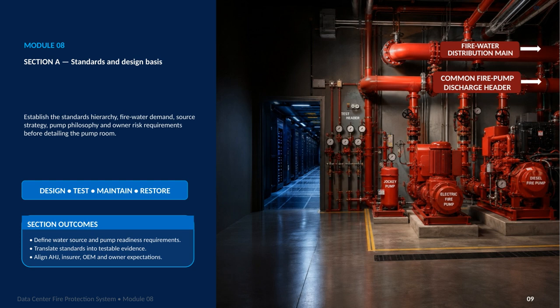First, we'll define what makes the water source acceptable and what readiness requirements apply to the pumps. Second, we'll translate standards into testable evidence, so compliance can be demonstrated rather than assumed. Third, we'll align the expectations of the authority having jurisdiction, the insurer, the equipment manufacturer, and the owner. Finally, we'll connect those decisions to the physical arrangement, including the fire water distribution main and the common fire pump discharge header. Establishing this foundation early helps prevent later conflicts between design intent, acceptance testing, operations, and restoration after an event.